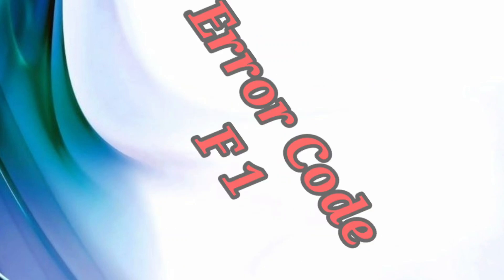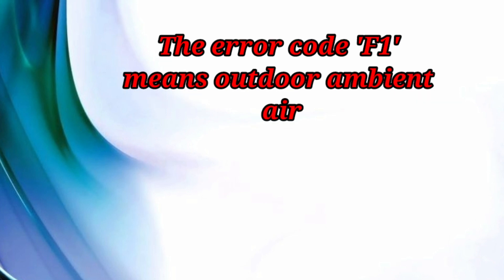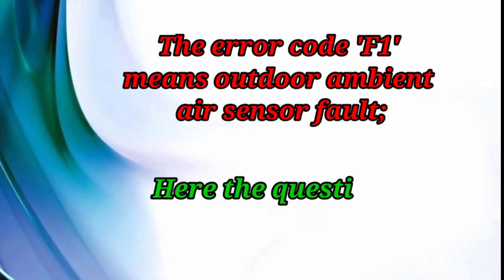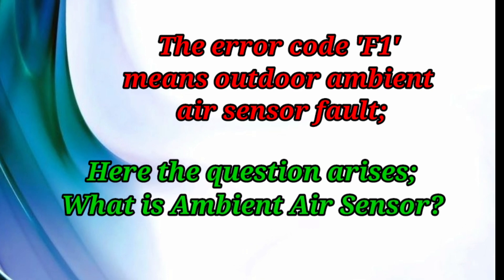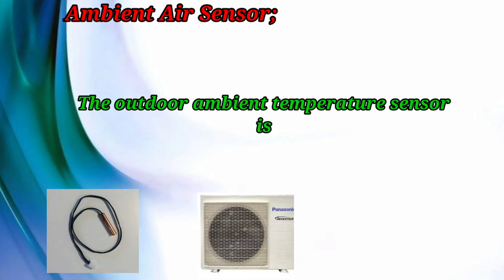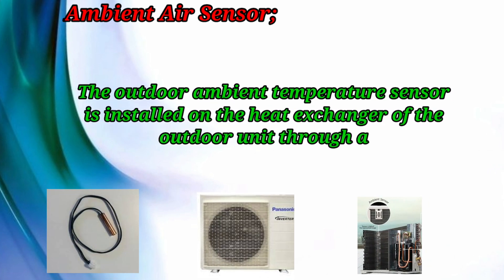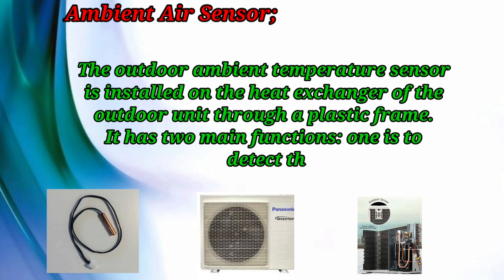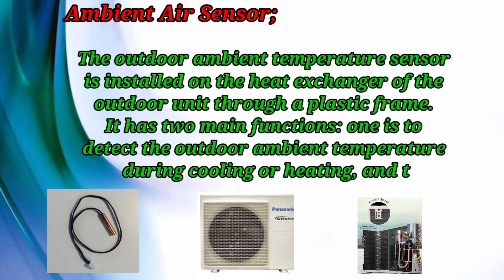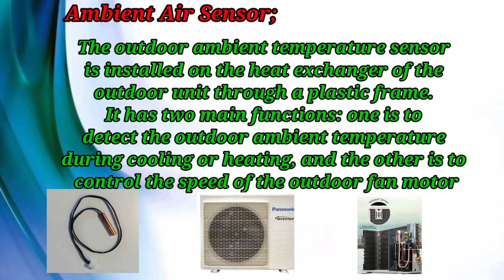Error code F1 means outdoor ambient air sensor fault. The outdoor ambient temperature sensor is installed on the heat exchanger of the outdoor unit through a plastic frame.